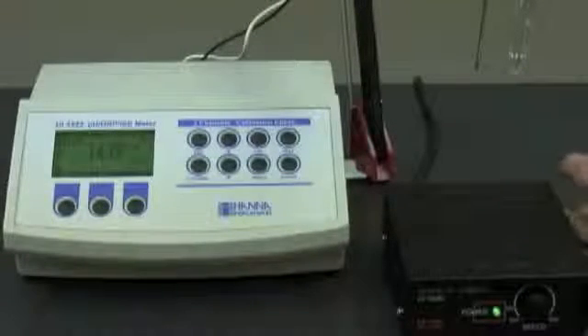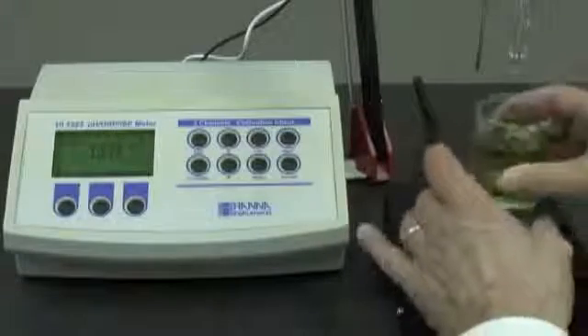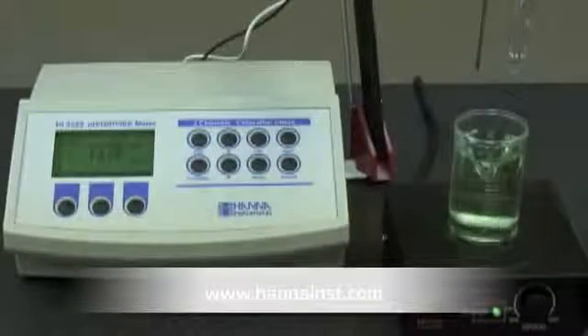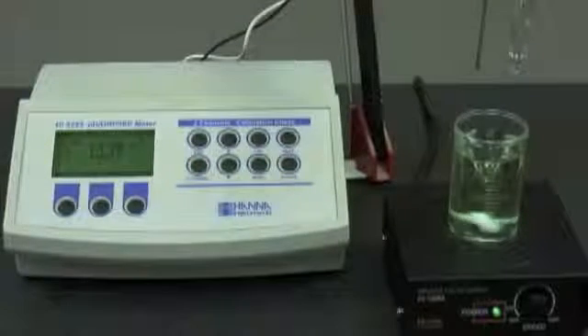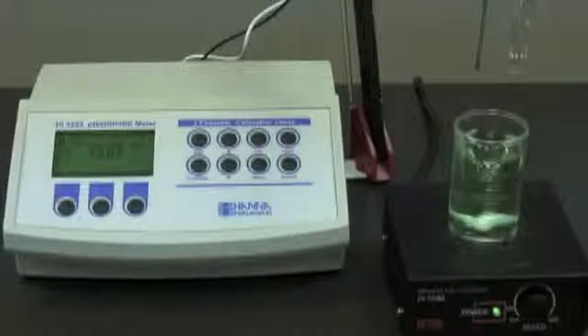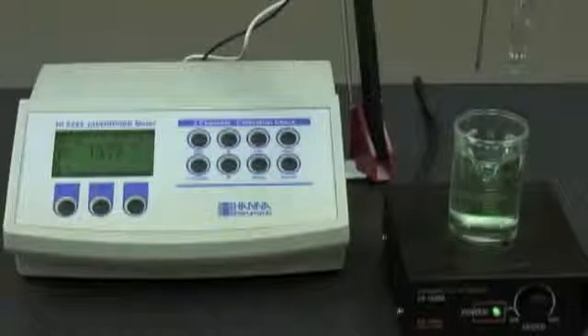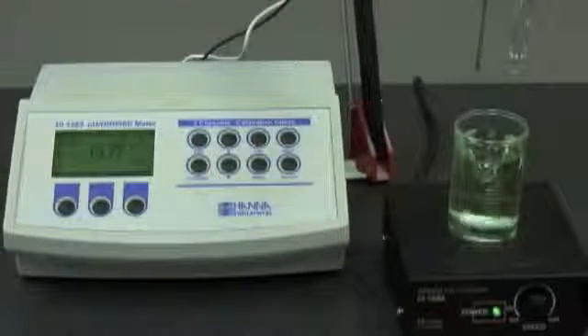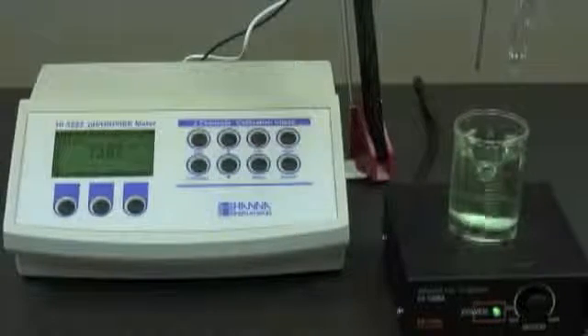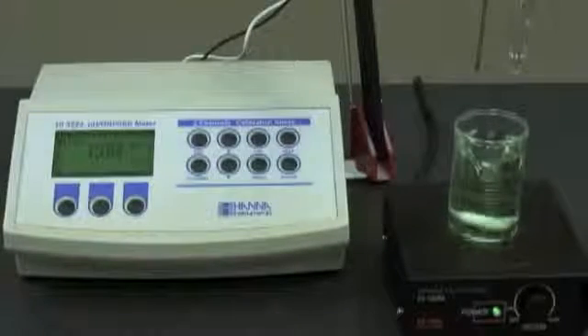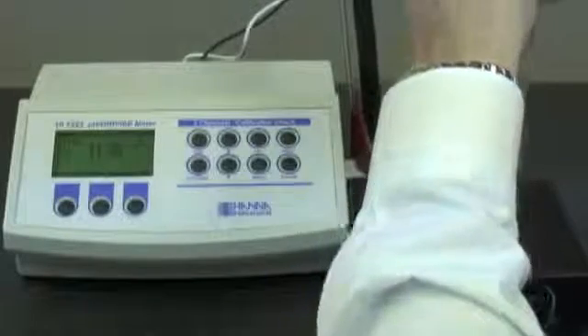The next thing I'm going to do is take my buffer, which in this case is number 7. And just a side note, as you can see, I put my buffer onto a magnetic stir. It's extremely important to do this in a laboratory setting because you want to make sure that your buffer solution remains homogeneous at all times. So since I've done that, I'm going to go ahead and lower my probe into my buffer.